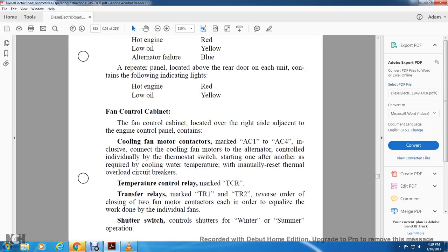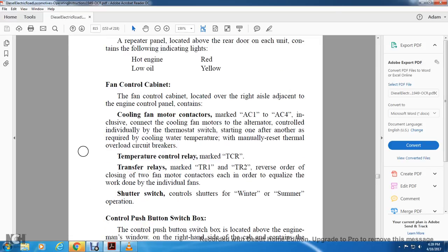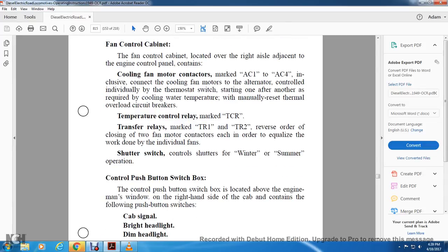Manually reset the thermal overload circuit breaker, the temperature control relay, and the TCR transfer relays marked TR1 and TR2. Reverse the order of closing the two motor fan contactors each time in order to equalize the work done by the individual fans. The shutter switch controls the shutter for winter and summer operation.